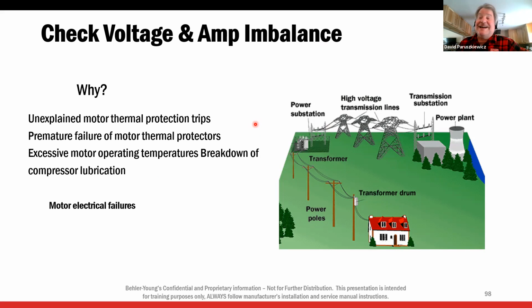So check those. High and low voltage. This is another one I can't stress enough. Check your voltage. If you got 250 volts, or 248 even, you need to start putting some voltage protection on these things. If you get 255, your voltage is high. Something needs to be done with it. Well, the old equipment, I know what old equipment used to do. The compressor would run on whatever you gave it. Well, we're going to have more and more electronics hitting this equipment. And it's not just ours. So how high the voltage is is just as important as voltage imbalance anymore. If the voltage is too high, we've got to do something with it. It'll lock those motors out. And if we're sitting right at the limit, you're going to have sporadic problems where you're locking motors out. It needs to be addressed.